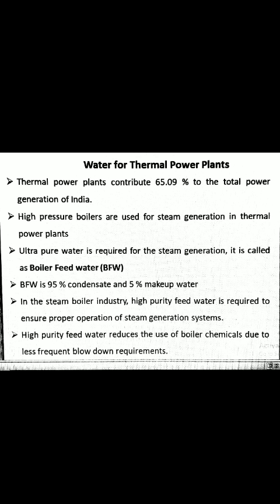The purity requirements for any feed water depend on how much feed water is used as well as what the particular boiler design can tolerate. High purity feed water reduces the use of boiler chemicals due to less frequent blowdown requirements. Lower blowdown frequency also results in lower fuel cost. Scale buildup is reduced due to a smaller concentration of impurities in the boiler feed water. The lower level of impurities also reduces corrosion rates in the boiler. When the boiler is used to run a steam turbine, turbine blade erosion is reduced due to higher purity steam generated.